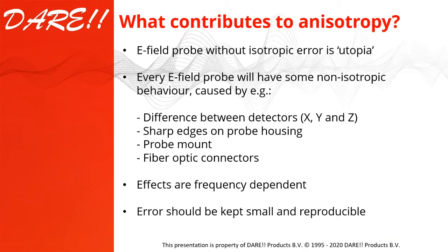In the past, we also started with our first laser power probe being a cubical probe. A cubical probe is okay at lower frequencies. The higher you go in frequencies, the sharp edges on the cubical probe will cause resonances, will cause eddy current effects, which will give a disturbance on the field. So it's better to have a spherical probe. A spherical probe, by definition, does not have very sharp edges.